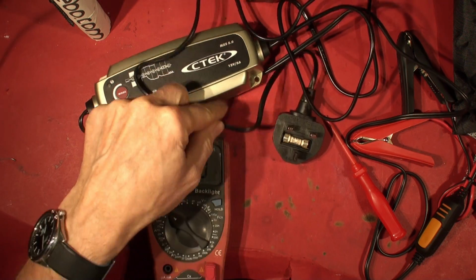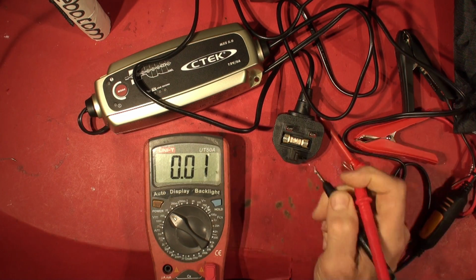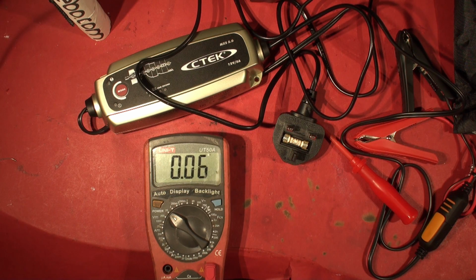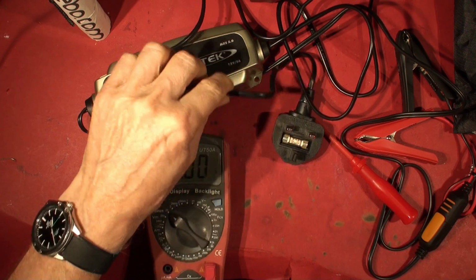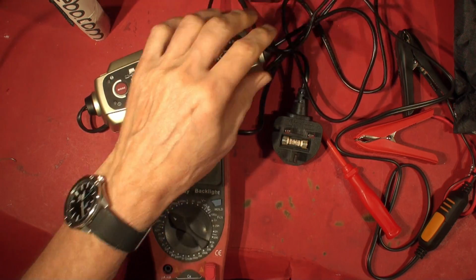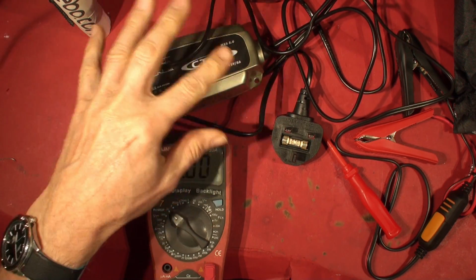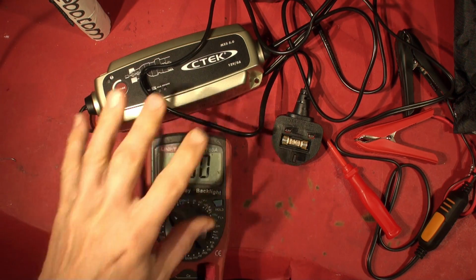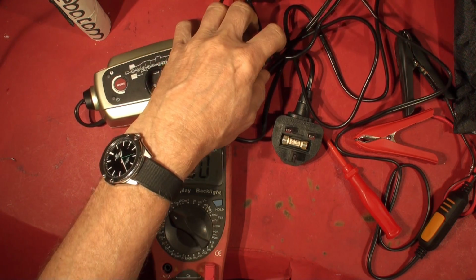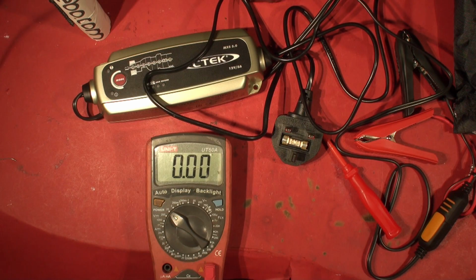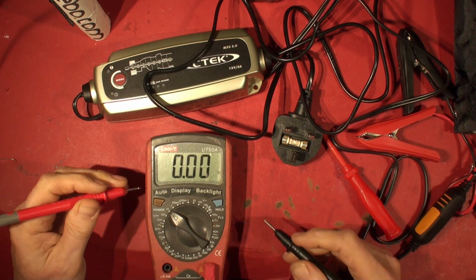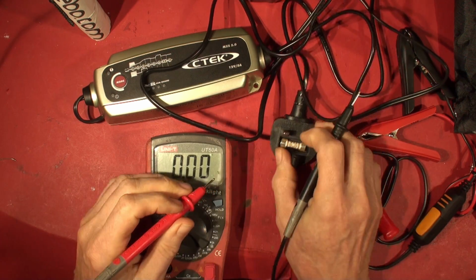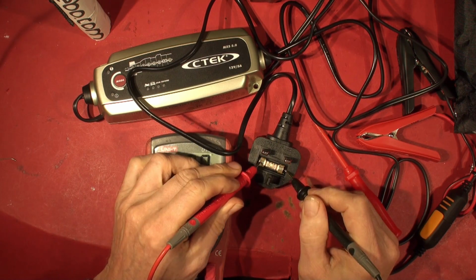This is like a 5 amp cable. So really the object of this fuse here is just to protect the actual line cord, the mains lead, because there's another fuse inside which protects the device. So if there was a dramatic short or a catastrophic short on here, it could burn the wiring out rather than blow the fuse. It would probably blow the fuse, but it's still not right. According to safety standards, it should be a 3 amp.